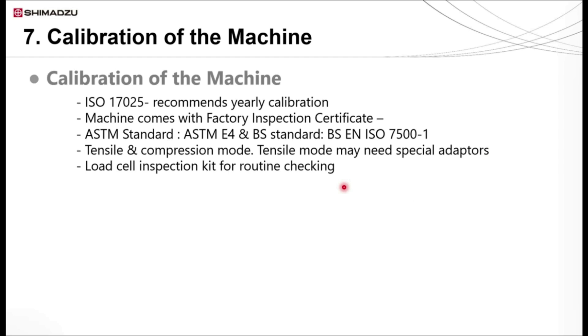For force calibration in the Middle East and Africa region, normally customers follow either ASTM E4 or BS EN ISO 7500-1. Both have some minor differences, so it is better to specify the standard in advance. Calibration can be done in tensile or compression mode. Does the supplier know your requirement in advance? For routine inspection, you may buy a load cell inspection kit from the supplier and you can check the accuracy of the load cell on a weekly or monthly basis.